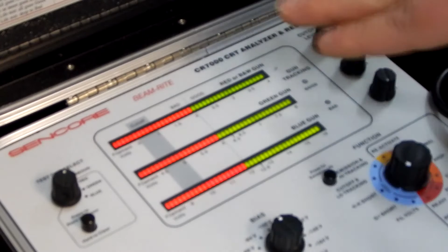Okay, so the first test we've got here is the filament volts. The first thing you want to check for is a G1 short, which is the different grids, you've got a heater cathode, then you've got your other tests up here which test the gun's life and stuff like that. So we'll switch it to that. Now this is in the green, which means that there's no G1 short. If these drop down or go into the red, that means there's a short in the tube, and you'll get things like flaring or sparking or problems with the tube of that nature. So that's good. We don't need to adjust that.